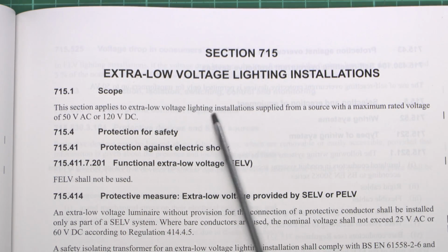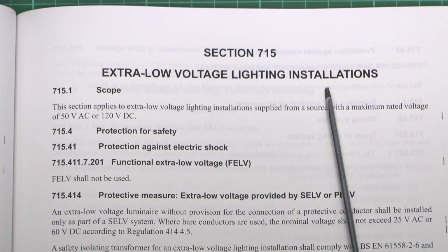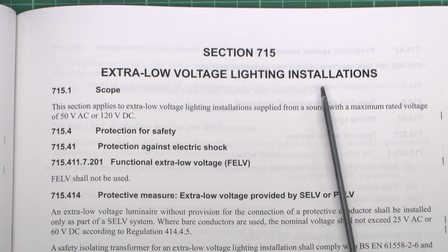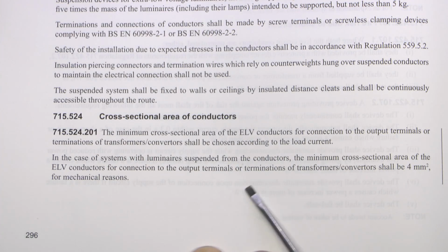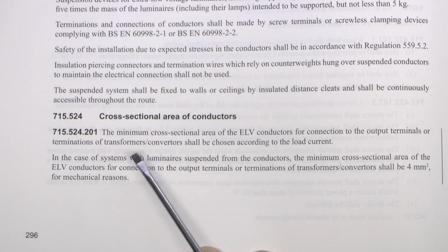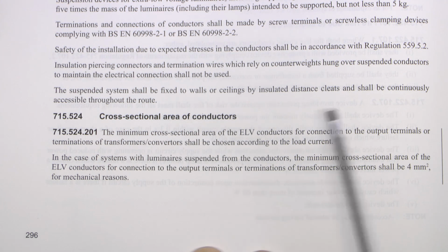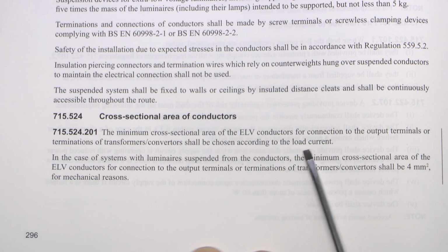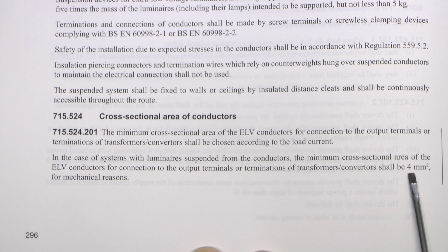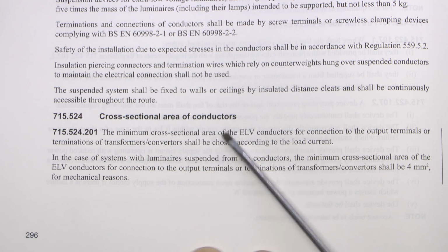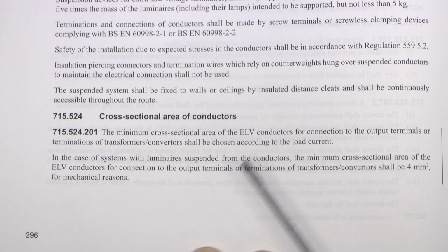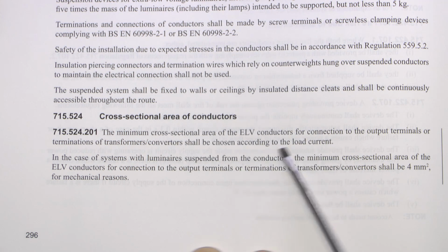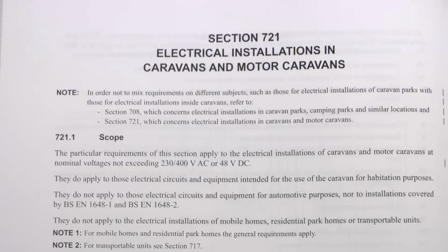Section 715, extra low voltage lighting installations. There's just one change here, and it's this one, 715.524.201. What we've now got is that the minimum cross-section area of the conductors shall be chosen according to the load current. So pretty obvious stuff there. And then the bottom part here is the minimum size of 4 square millimetres for mechanical reasons. Previously there was actually a list of various things, including the length of the conductors and other things, but now it's just a question of minimum size, of course based on the load current.